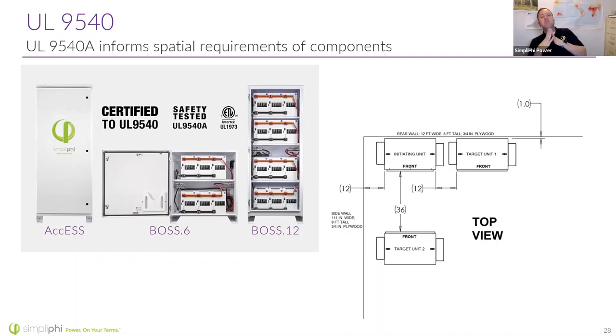Let me pause on this. In the 9540A test, where we subject these batteries to a thermal runaway event, there is no inverter involved—there was no inverter in that test room at the UL labs.